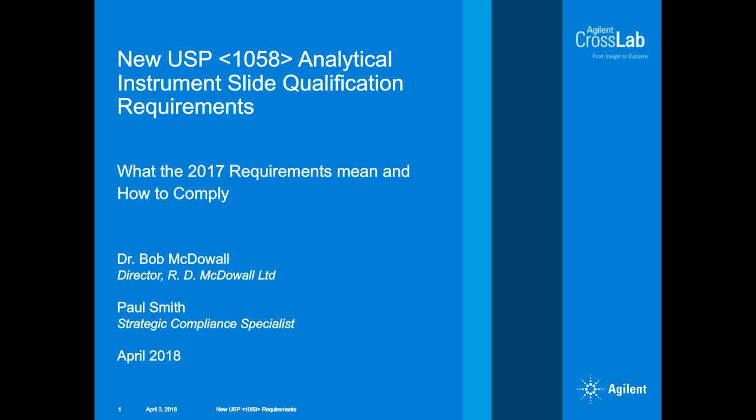And so nothing further to add to Bob, really. I think, in my experience, it depends fundamentally on what you include as system suitability tests. Historically, lots of companies performed what I would call good chromatography practice, where they had valid, meaningful system suitability tests. I think Lean Sigma may have resulted in what might have been good practice being reduced. So in our experience, we've even written a paper around risk assessment of HPLC that relates to system suitability tests.